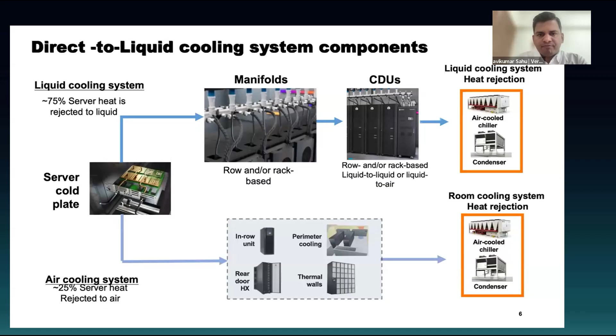So as we discussed earlier, we require liquid as well as air cooling. For air cooling, we can use a fan wall, or we can use a rear door heat exchanger. So whatever the 80-20% or 70-30% split, whatever the air cooling component is there, we have to use either of the three or four mechanisms.